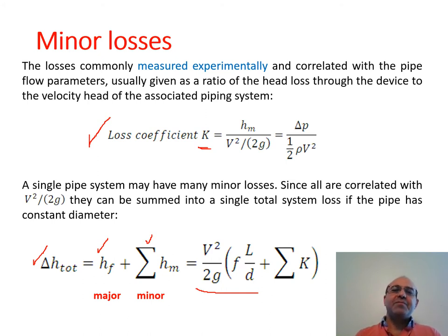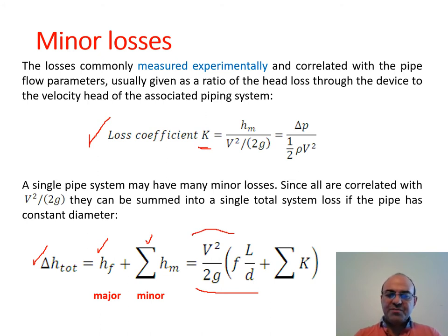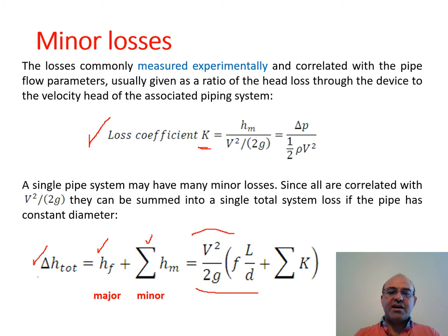The total head loss is h_total = h_major (Darcy-Weisbach) plus the sum of all minor losses. We count how many valves, bends, elbows, entrances, and exits we have to get the sum of all minor losses. Sometimes the sum of minor losses can be quite large, even larger than the major loss. Factoring out v²/2g gives: h_total = [fL/D + ΣK] × v²/2g.